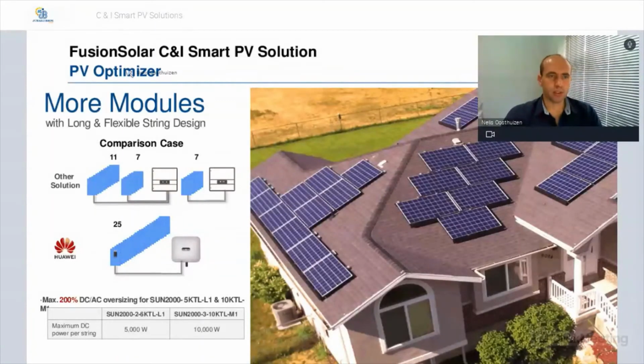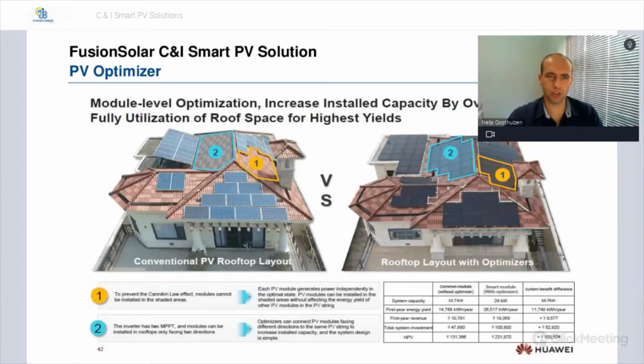So another advantage of using the PV optimizers is that you can have a maximum of 200% DC to AC oversizing, or a DC to AC ratio, when you're looking at a 5 kTL to 10 kTL. So this is more applicable to the residential. So if you want to know more about this 200% DC to AC ratio, make sure that you attend our residential webinars, or do make contact with us and we can assist you or provide you with more information on this.